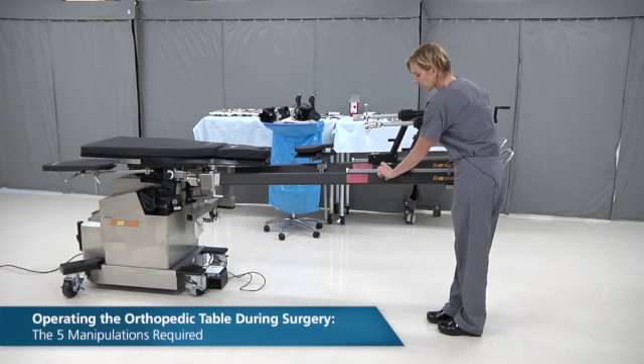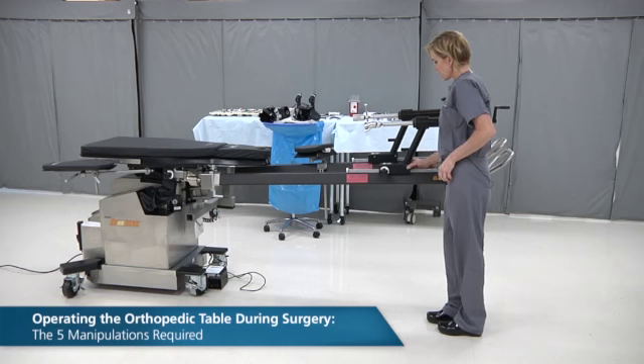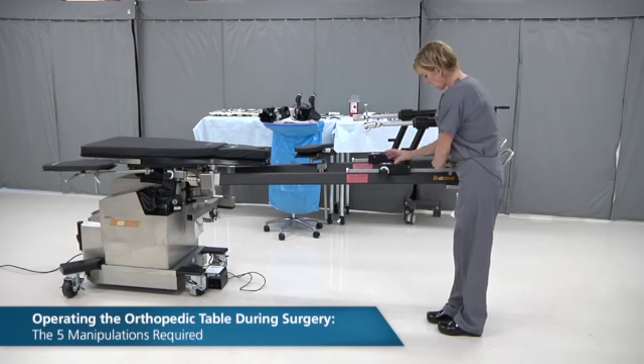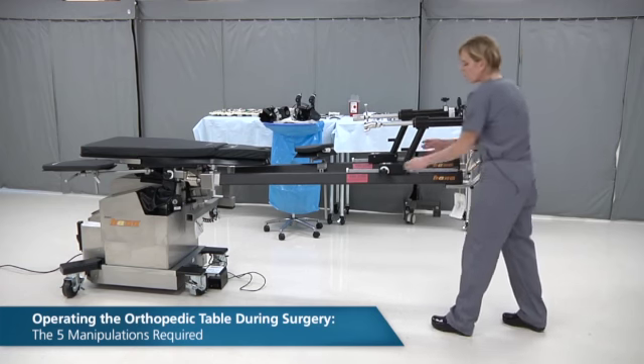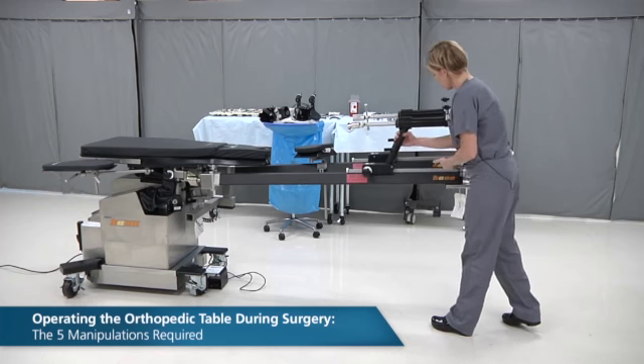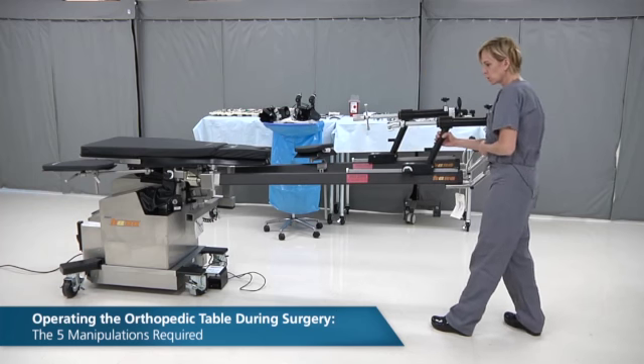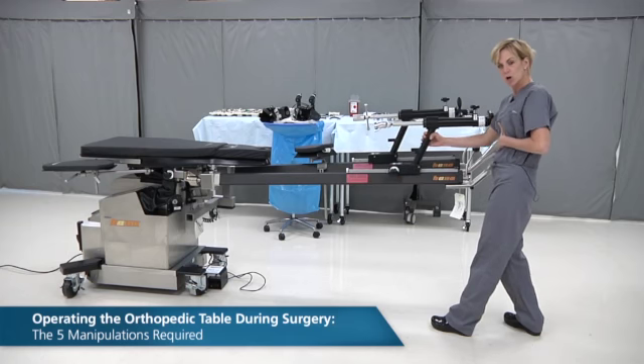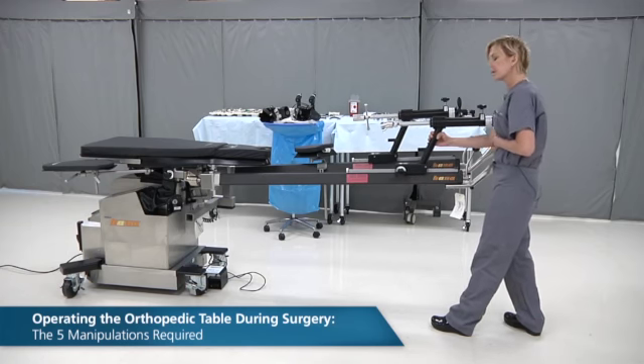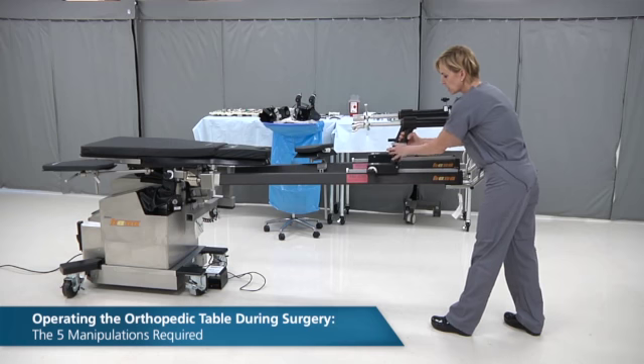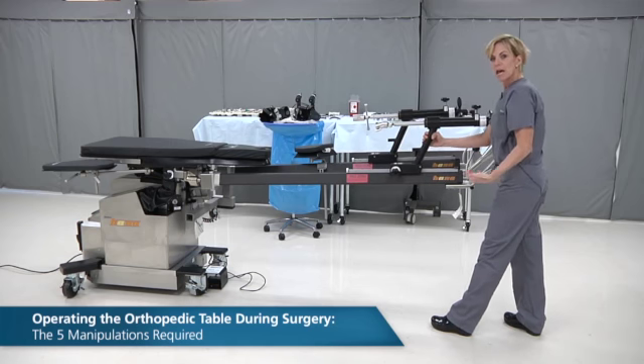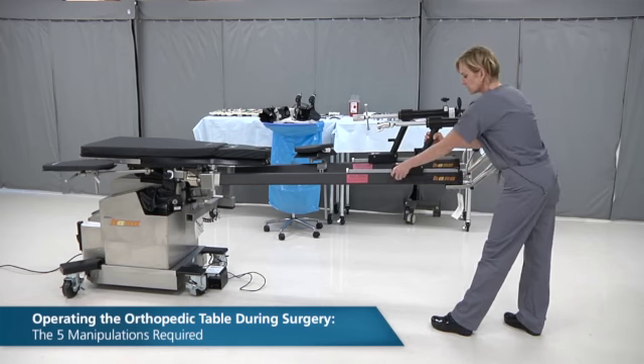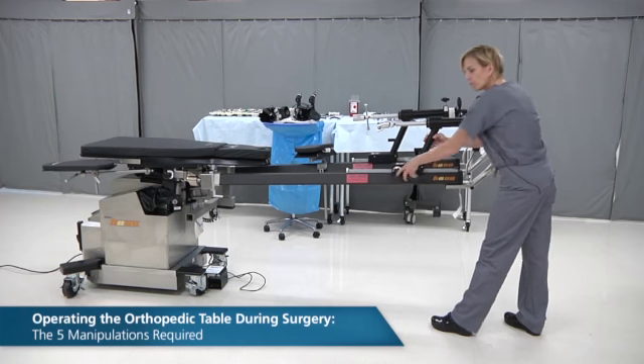Unlocking to the left or locking to the right allows this box to slide on this rail. What that will do, if it's unlocked, with just your hand, you mechanically pull traction on the patient's leg or relieve traction on the patient's leg.